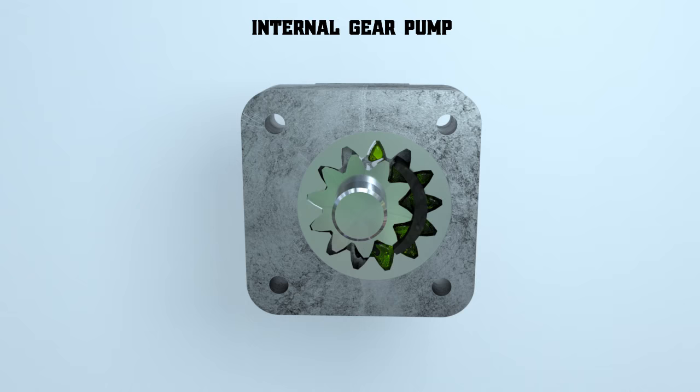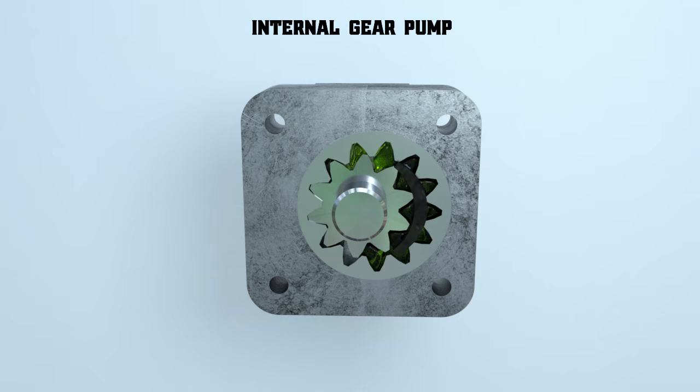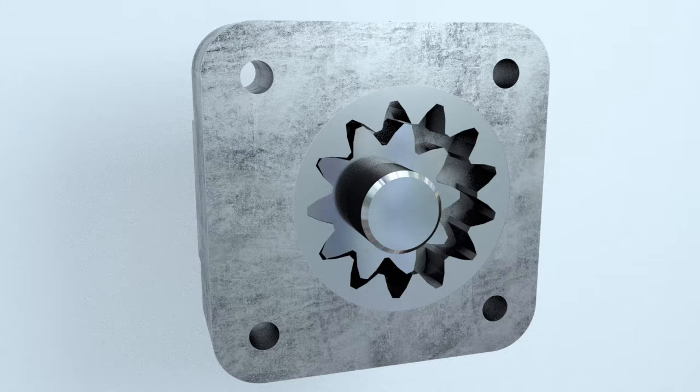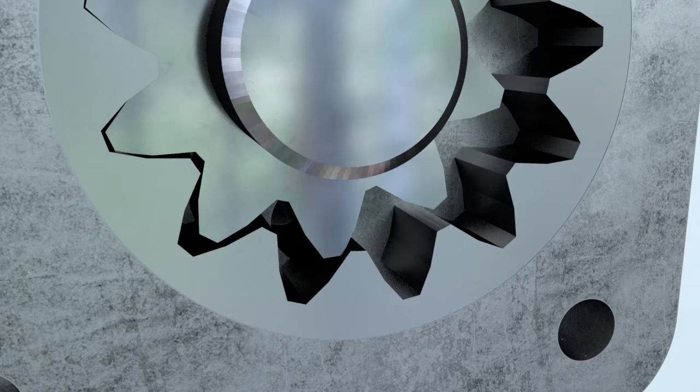Let's take a closer look at how an internal gear pump functions. The suction channel is located at the point where the gear teeth come out of the mesh, and the discharge channel is located at the point where they go into the mesh.